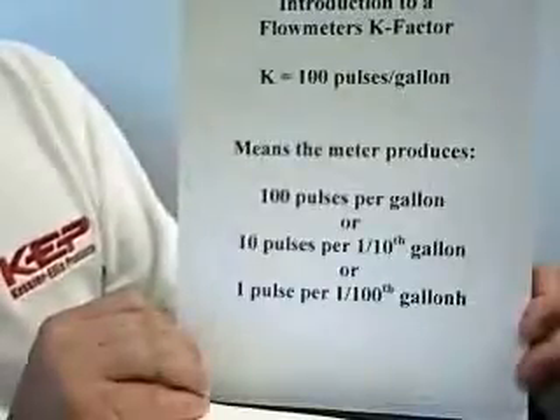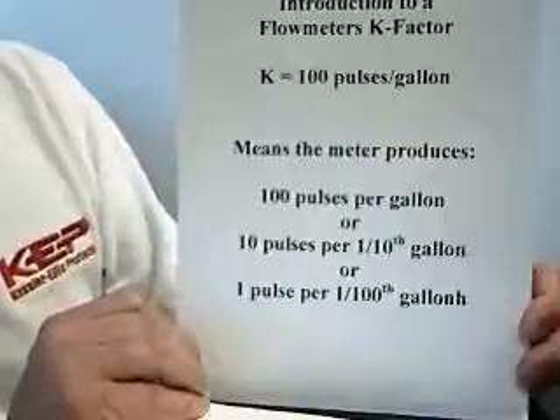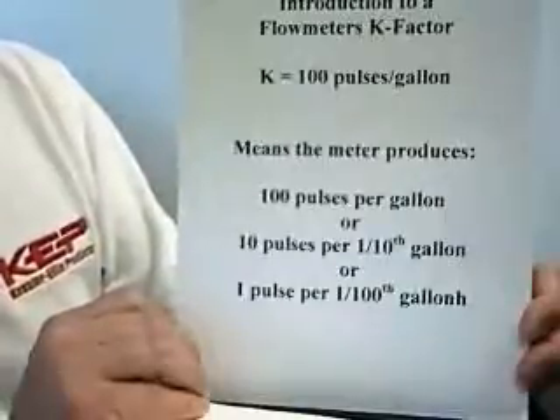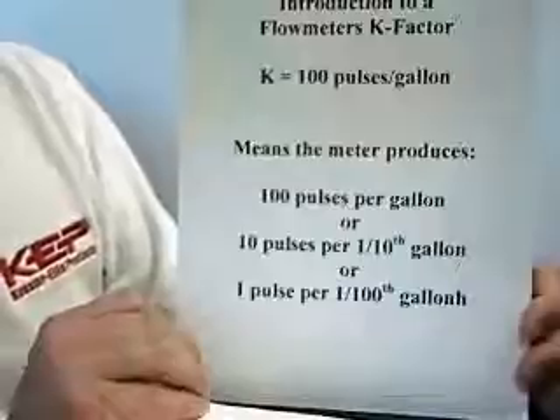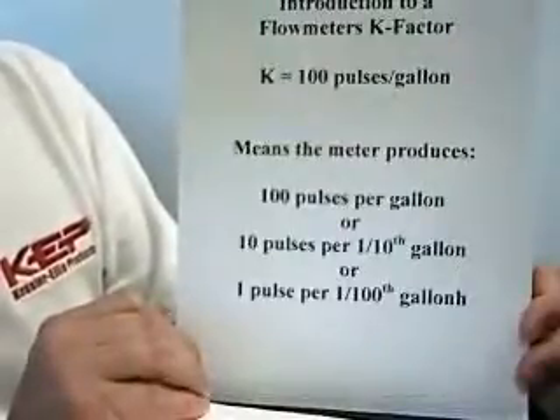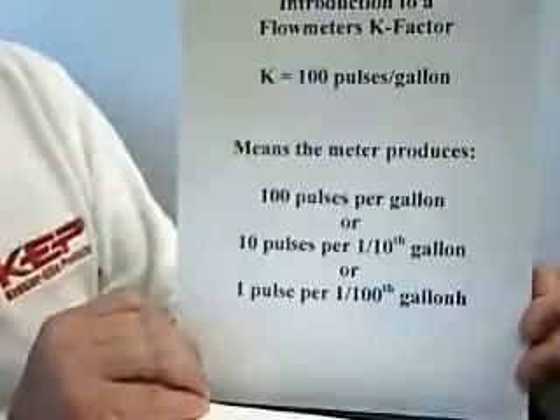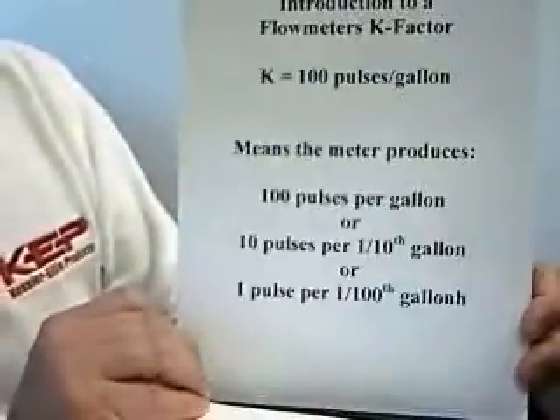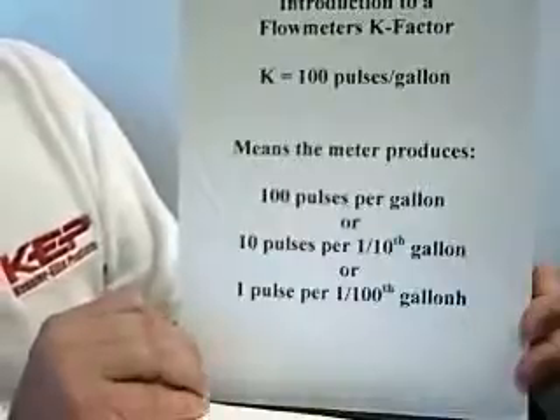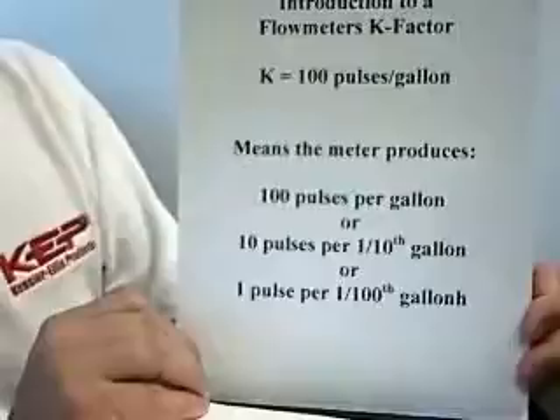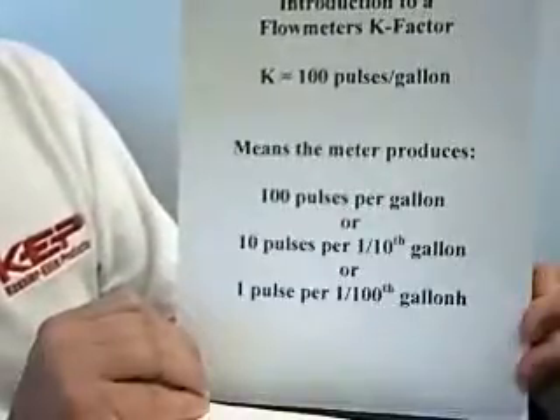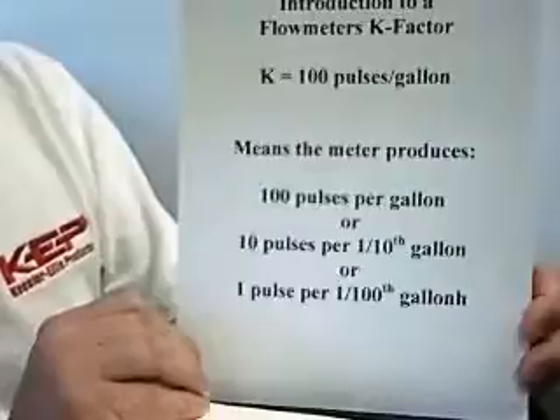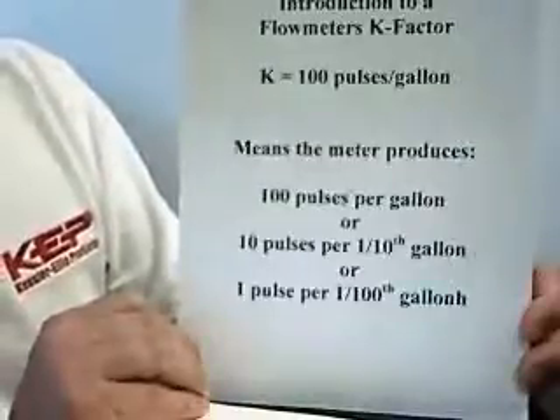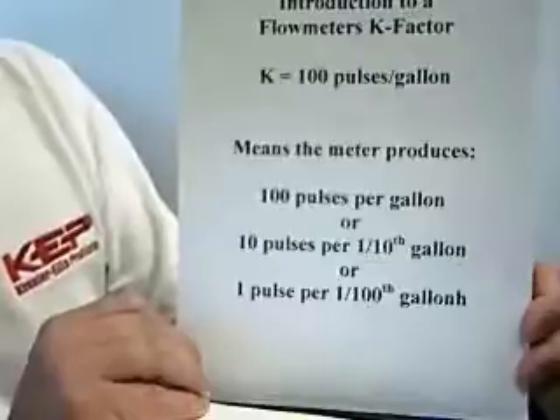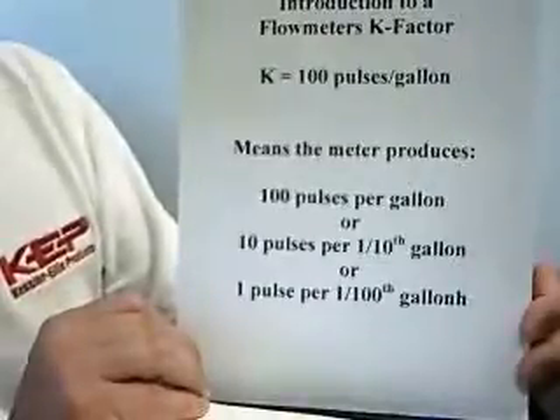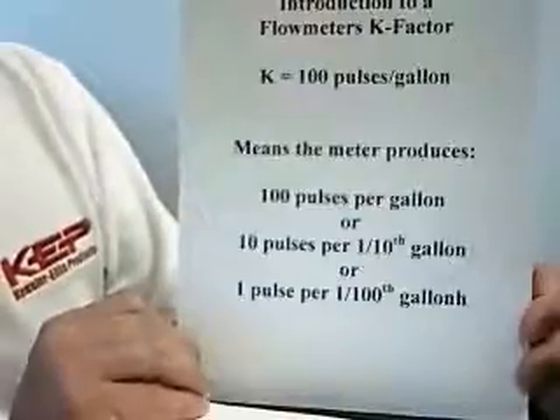If you wanted to have a resolution that is in 10th gallons or 100th of gallons, it's important to realize that 100 pulses per gallon could also be stated as 10 pulses per 1/10th gallon or 1 pulse per 100th gallon. This is important to begin your setup of the instrument to know what is the actual calibration for your sensor, as well as the flow range that it can measure over, and to know what the units that you desire to display on your indicator for the rate and the total.